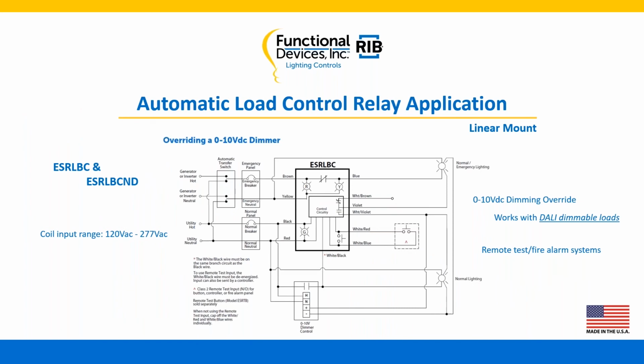Here you can see the override of 0 through 10 volt dimming. Again, over here on the right-hand side, you've got a white, violet, and a white. That's your 0 through 10 volt dimming override. Again, it's coming from a controller down below. So when normal power drops, we break that, we open that contact, so the normal emergency light can have full brightness. Again, the code says it has to.